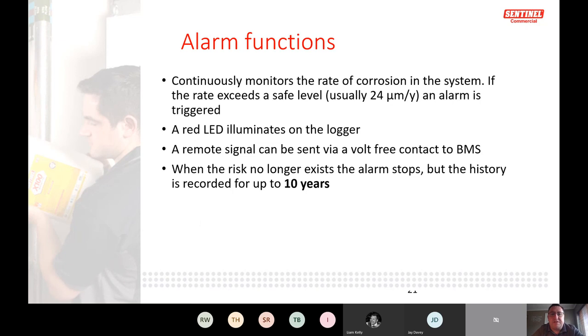The alarm threshold is preset at 24 micrometres per year. If it goes above that it automatically triggers a red light on the logger, an audible alarm, and a remote signal to the BMS. When the risk no longer exists the alarm stops, but the event is recorded — data can be retained for up to 10 years.